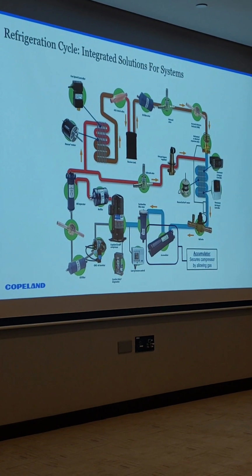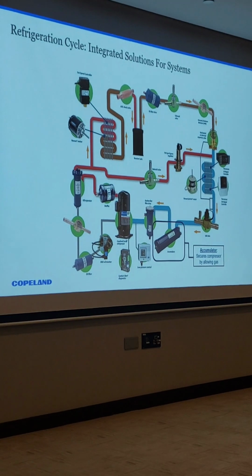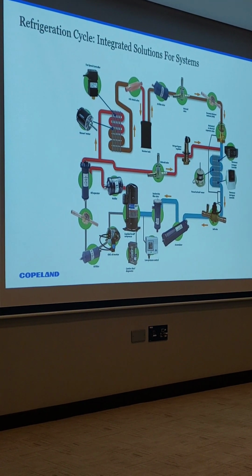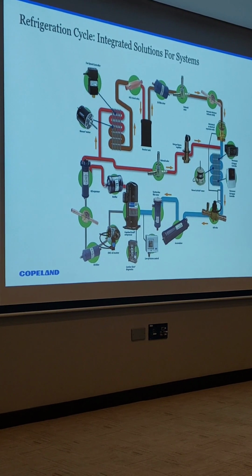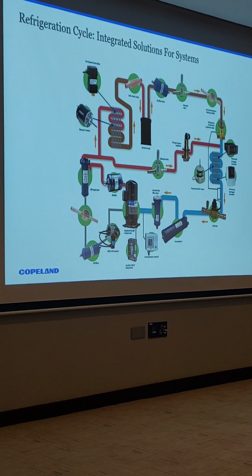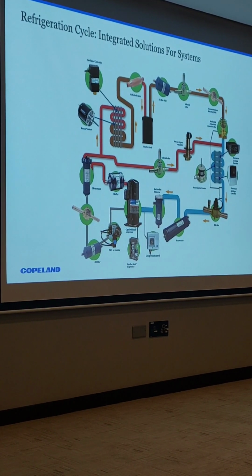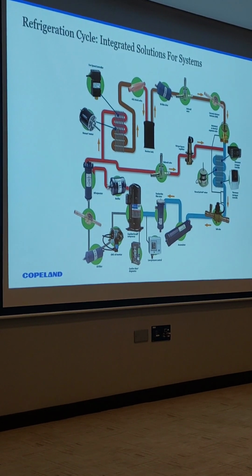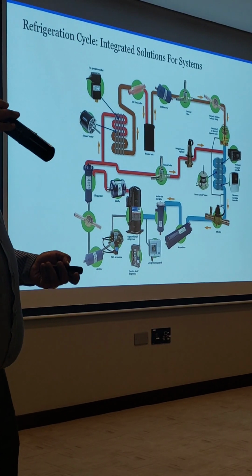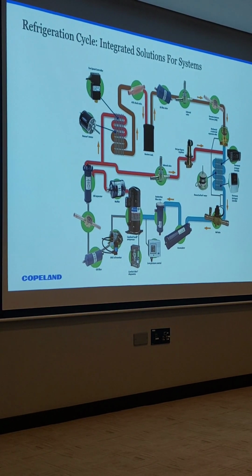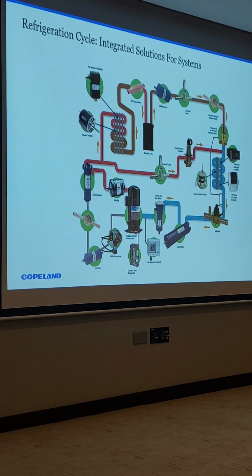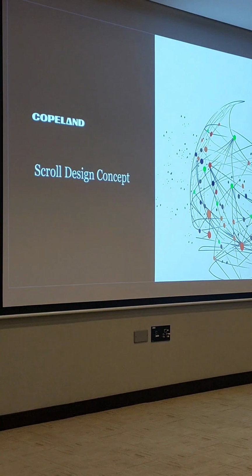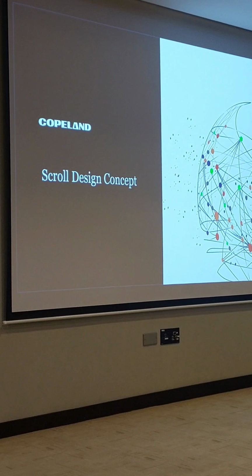We have accumulators. We also have accumulators for some certain refrigeration applications, and also accumulator used for fresh air AHU applications. So when it comes to fresh air AHU, the load keeps on changing based on your ambient. So at low ambient condition, there is a possibility of liquid coming back to the compressor. To arrest that, a lot of manufacturers use accumulator in the suction when it comes to fresh air application. That's it on the product wise.